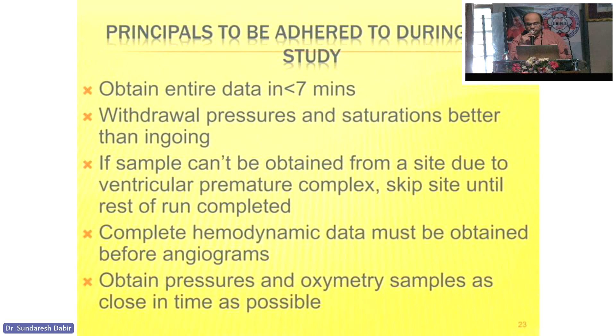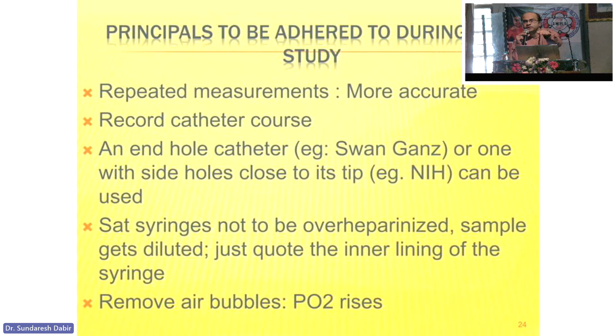End-hole catheters are important. It's something that they'll ask you. End-hole and side-hole catheters. Berman is a side-hole catheter, classically used for injecting into a ventricle, because when you inject through a pressure, like into a chamber, you don't want perforation. So you don't want an end-hole catheter going and hitting your wall. That's why you've got side holes and pressure dissipating, typically pigtails, or if you have a Berman catheter. Vis-a-vis, if you compare this with an end hole, for example, a wedge catheter, you need it to be end hole, because once you wedge it, you want something beyond that. That is the LA pressure.